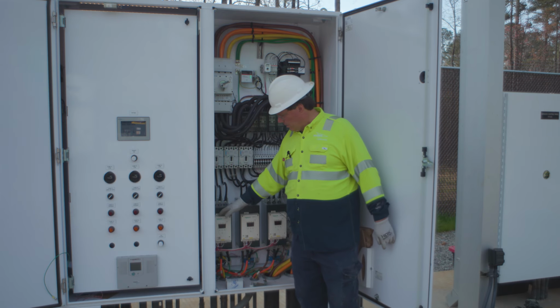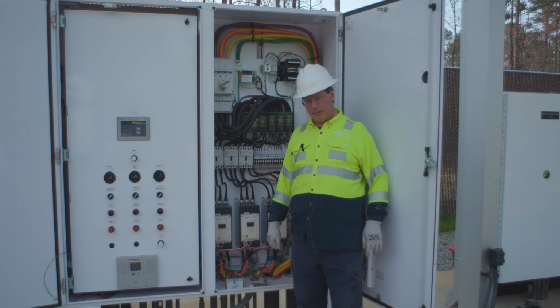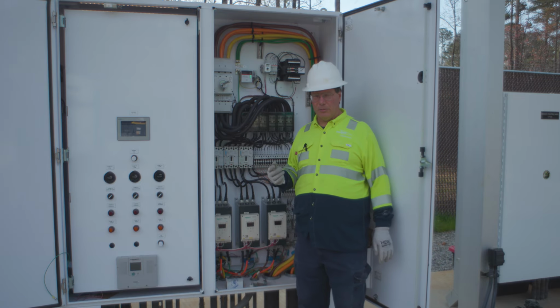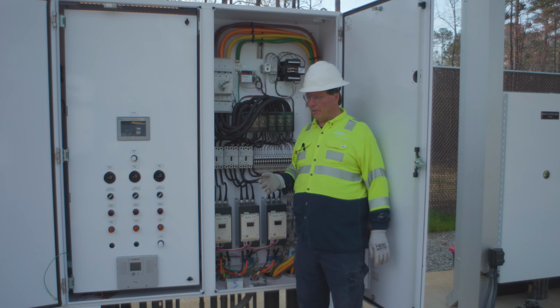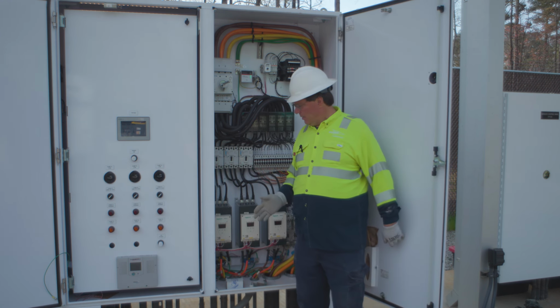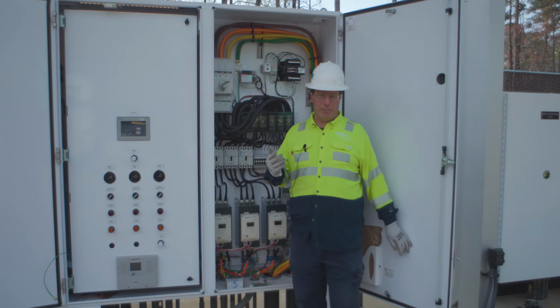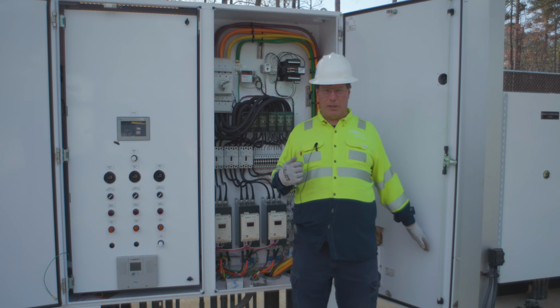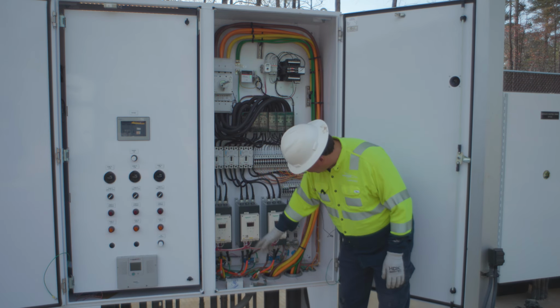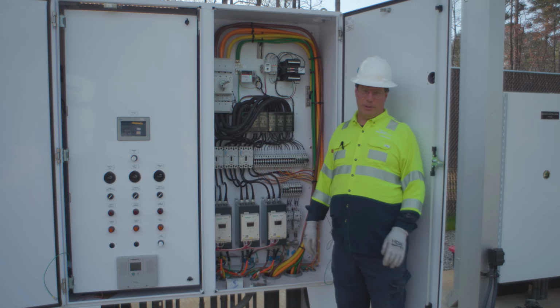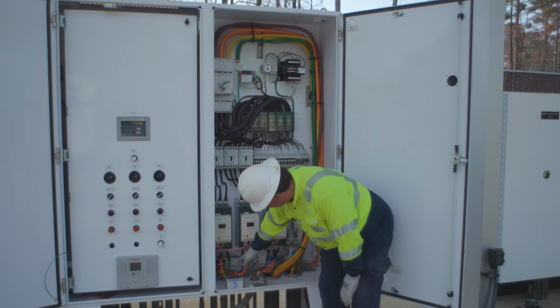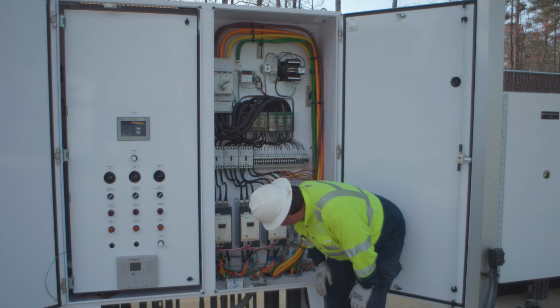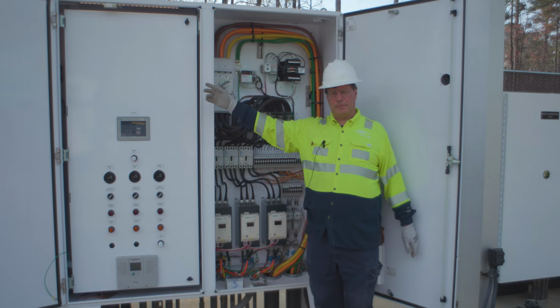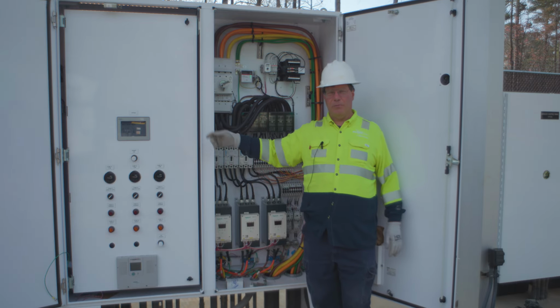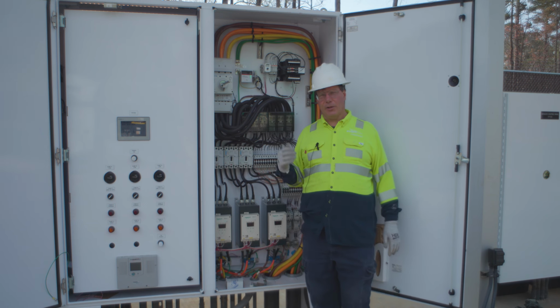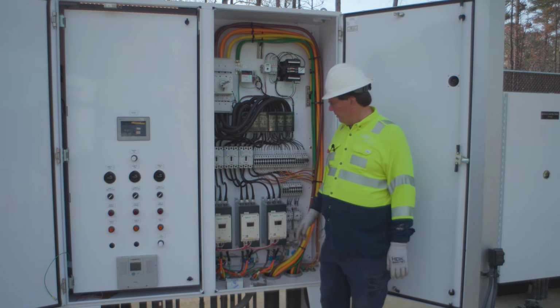The ATS-22 model soft start has a built-in bypass contactor. So after it completes its soft start, it'll close the bypass contactor and run 100% voltage down to the pump until it's ready to turn off, at which point it opens the bypass contactor and does its reduced voltage soft stop. Coming from the soft start, it goes directly to the pumps through those terminal cabinets we looked at earlier. Each one of these pumps has a CT on it, which monitors the current, and that current is sent back to the PLC, which we'll go over last, and they're able to look at the current when the pump runs coming off the soft start.